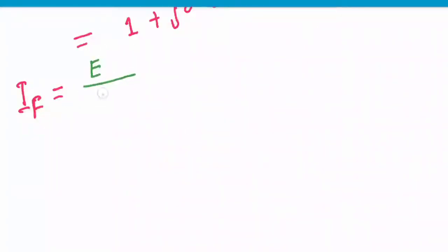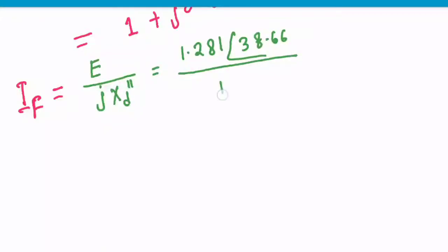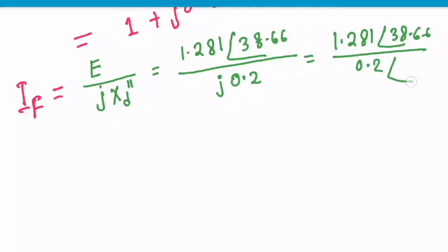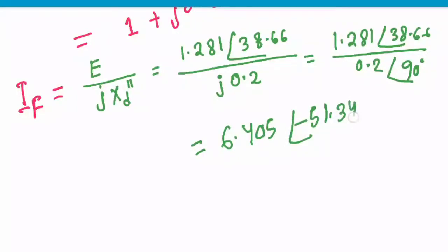The fault current equals E divided by j·Xd double prime. This gives 1.281 angle 38.66 divided by j·0.2, which equals 1.281 angle 38.66 divided by 0.2 angle 90, resulting in 6.405 angle minus 51.34 degrees per unit. So the fault current is 6.4 per unit, which is 6.4 times the rated current. Thank you for watching.